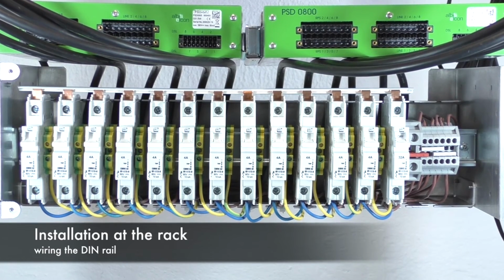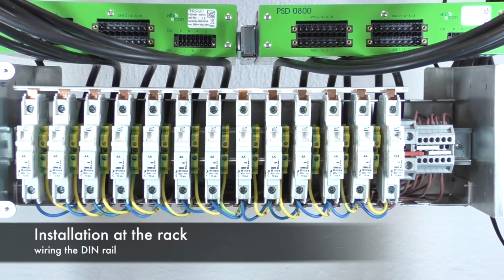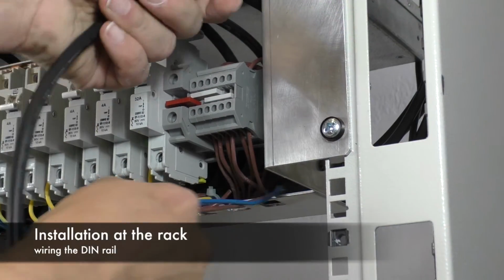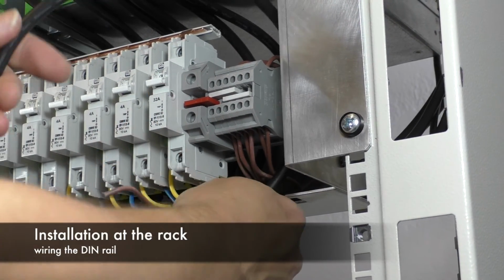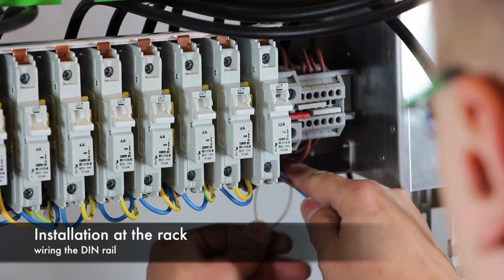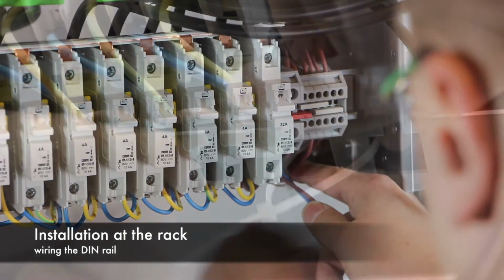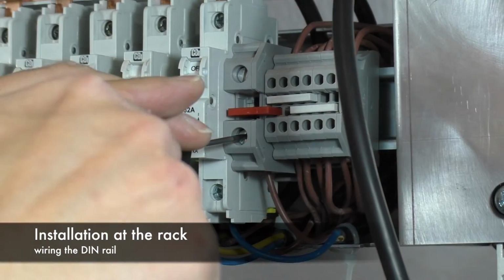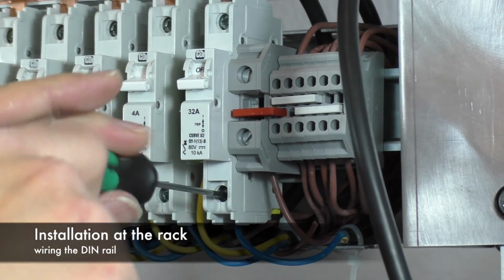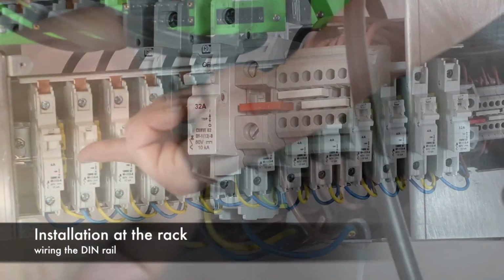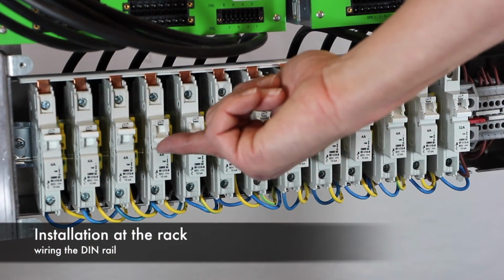Strip 150 mm of the access line, seal with ferrules. Thread the access line through the top recess of the cable guide. Secure the cable at the lower leg of the cable guide. Connect the blue core cable to the 32 ampere circuit breaker and the brown core cable to the large feed-through terminal. The circuit breakers are now ready to be switched on.